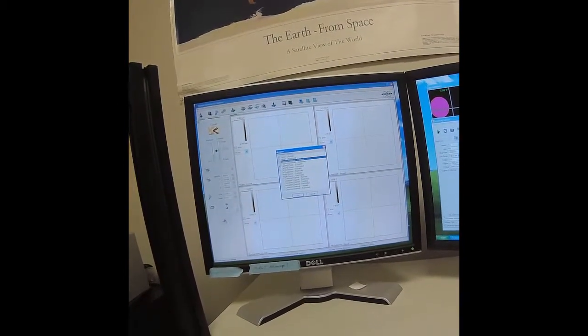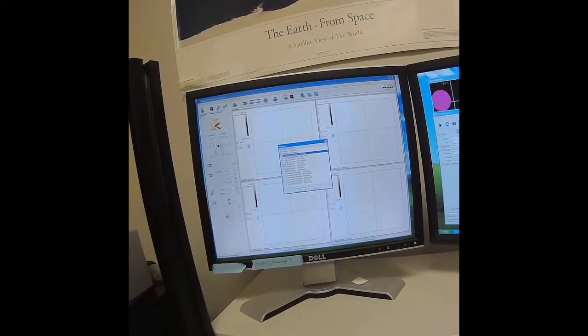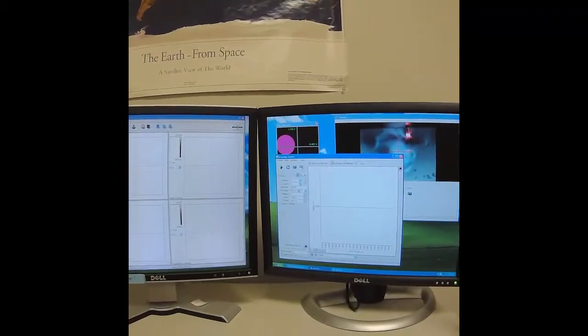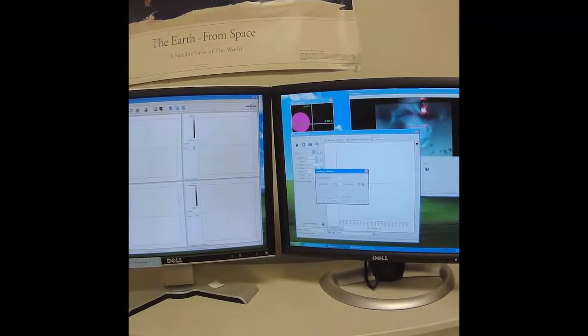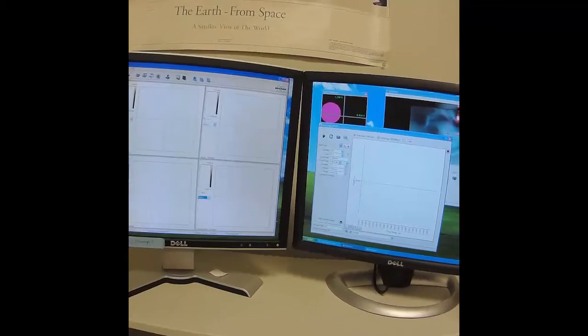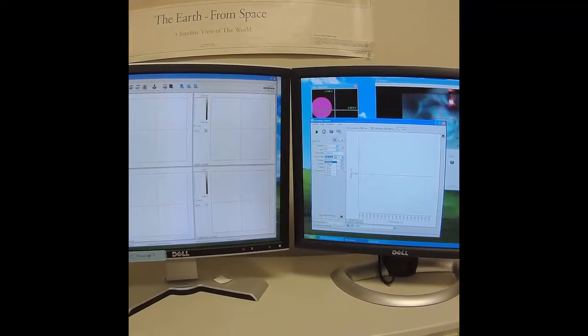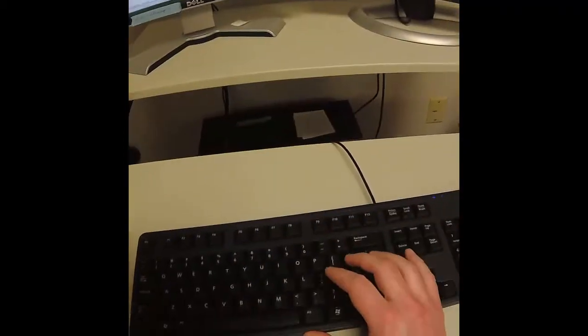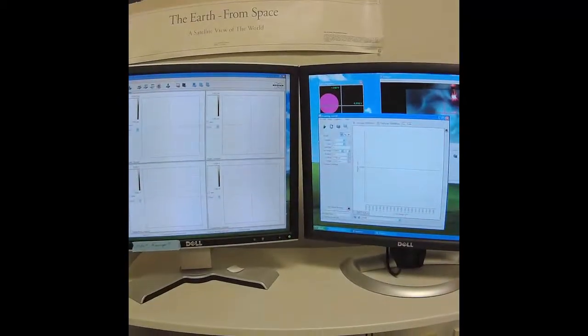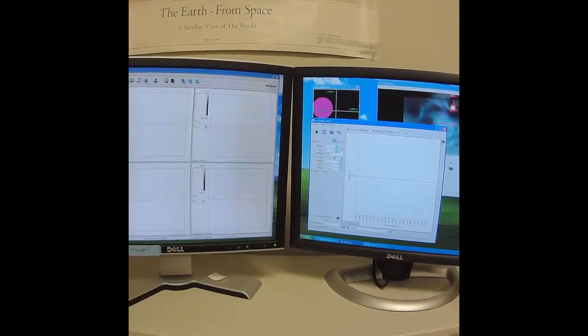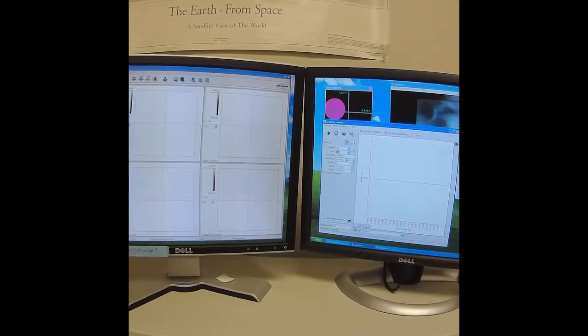So height forward and backward is useful. Tapping amplitude we used in a different experiment. This time we're going to look at phase forward and phase backwards. Okay, now check and make sure 10% overscanning. Let's start at a large area scan, and go slowly at low resolution to get an overview of what the sample surface looks like.